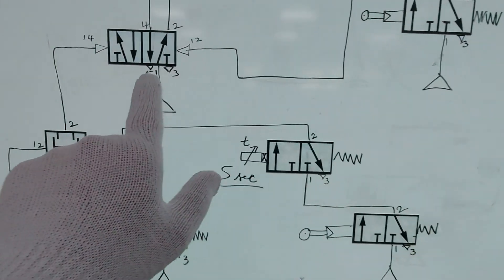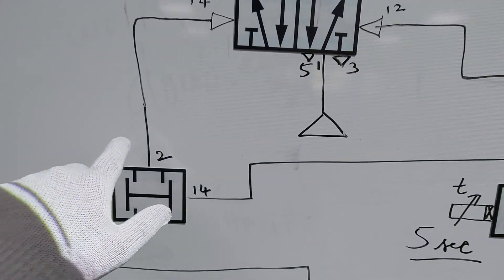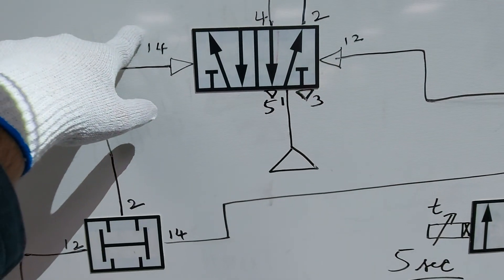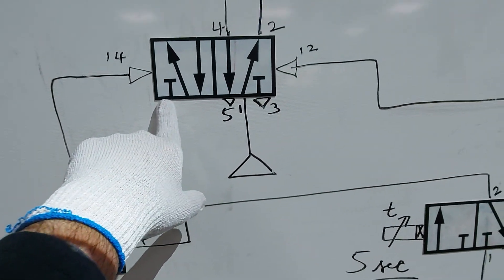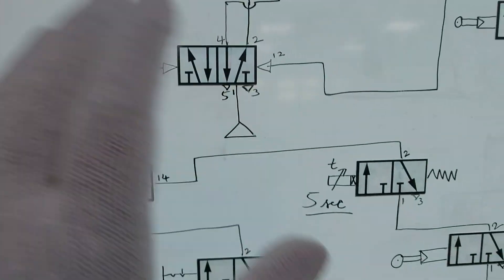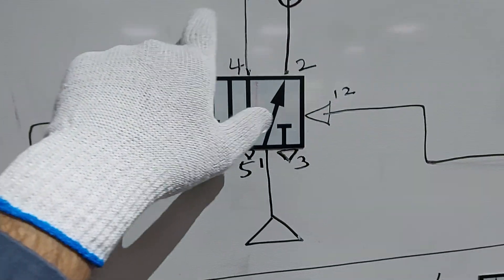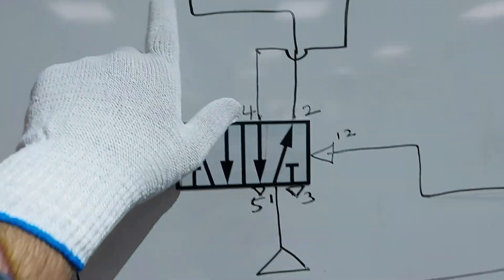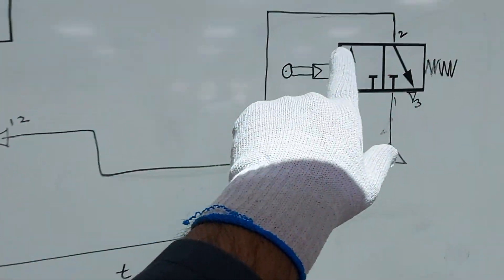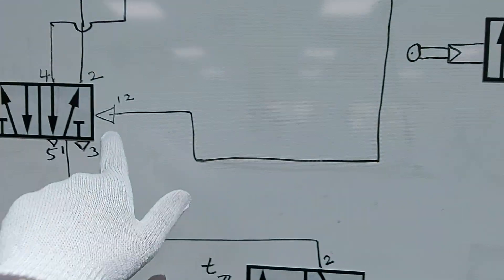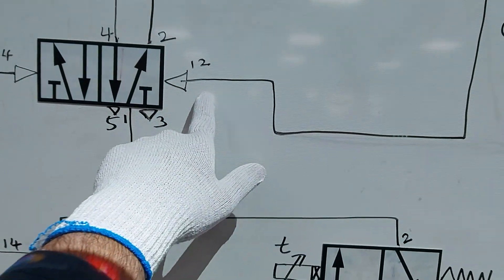We need to connect as per the port numbers. For example, port 2 from the dual pressure valve goes to ports 1, 4, and 14 of the 5/2 way double pilot valve. Port 4 of the double pilot goes to one side of the cylinder, and port 2 goes to the other side. Port 12 is connected here, and the output port 2 of the roller is connected to port 12 of the double pilot.